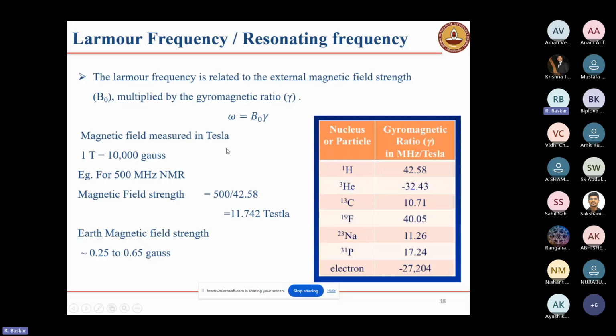Generally, magnetic fields are measured in Tesla. 1 Tesla equals 10,000 Gauss. For example, in 500 megahertz, the magnetic field strength is 500 divided by 42.58, the gyromagnetic ratio of proton, which gives 11.742 Tesla. This is the 500 megahertz magnetic field strength. Like this, we can calculate any instrument's magnetic field.